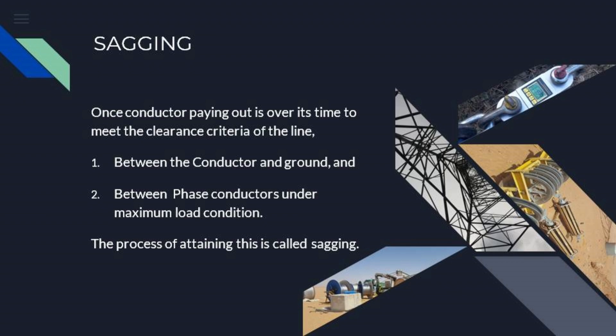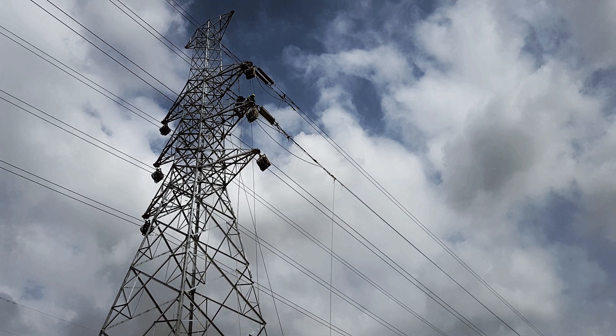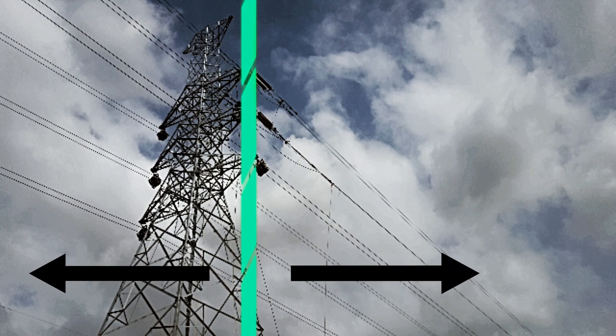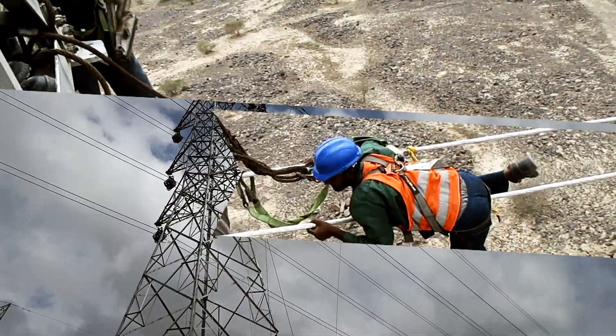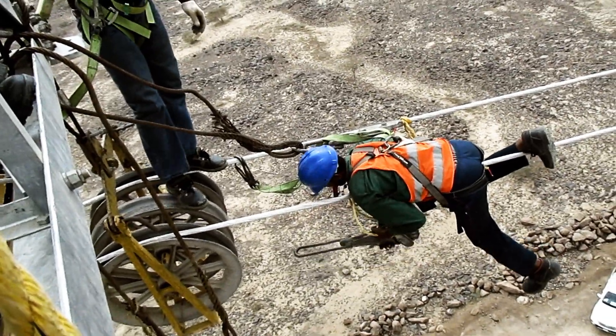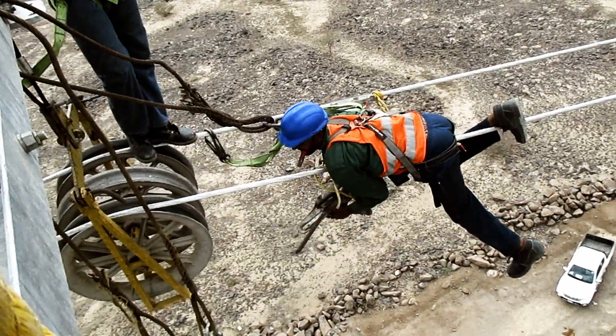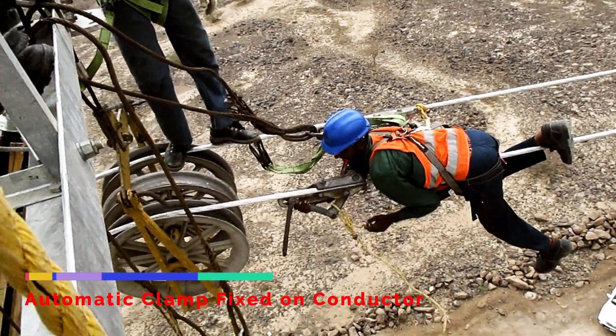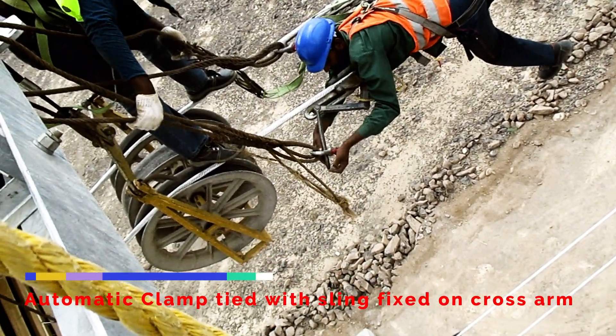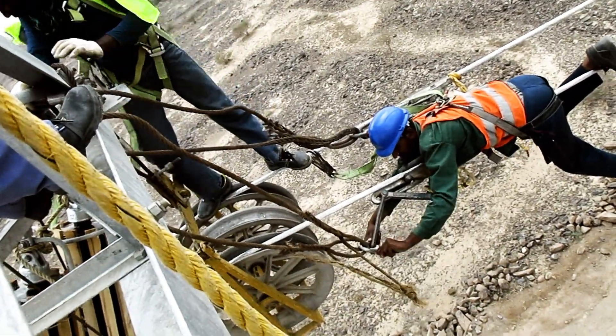Once the conductor paying out is over, it's time to meet the clearance criteria of the line — which is between the conductor and ground, and between phase conductors — under maximum load condition. The process of attaining this is called sagging. From the side view of the tower, we divide it into two zones: the sagging zone and the non-sagging zone. Our first step is holding the conductor in the non-sagging zone. An 18 or 20 mm wire rope sling is attached to the cross arm; the other end of the sling is attached to the automatic clamp fixed on the conductor. This is done to maintain the required rough sag tension in the backspan during sagging.